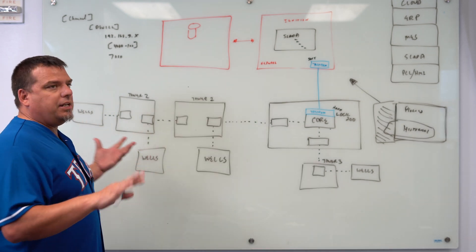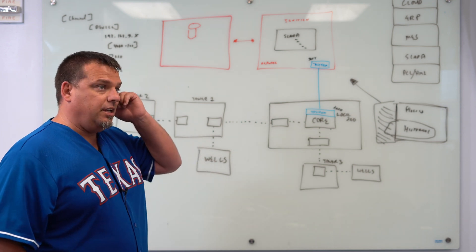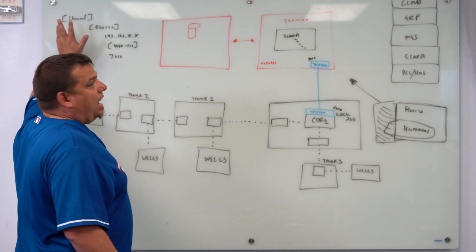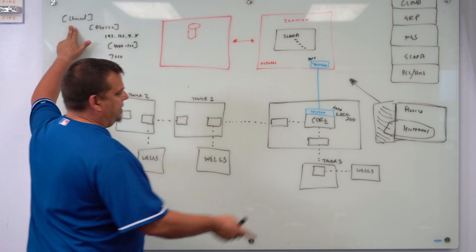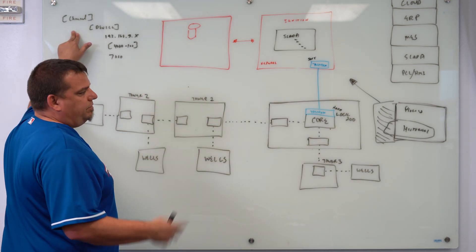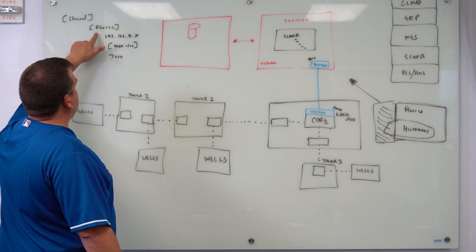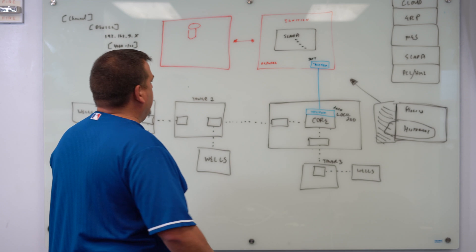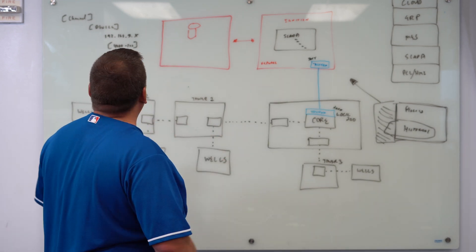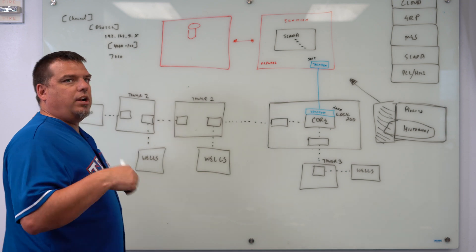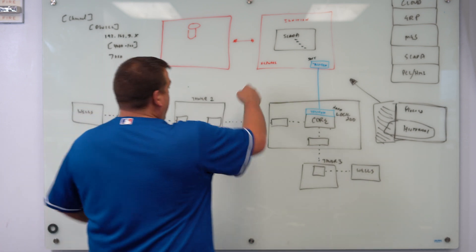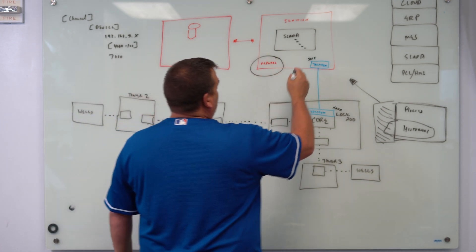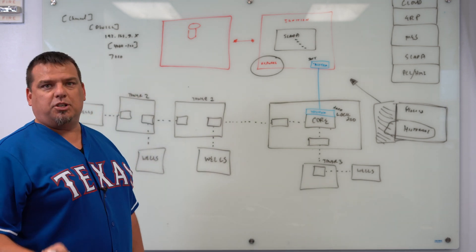The plan right now is we're just about done. We're actually ready to cut over tomorrow. We're going to be doing production testing starting Monday under this existing infrastructure. If you were to look at Kepware, we have somewhere in the neighborhood of - I think we've got a channel configured for every tower. We created a channel for each tower because we wanted to be able to group all the wells by tower for communication diagnostics reasons. We have a channel for every tower, and then we have all the wells listed in the device, or all the ABB total flows under each tower. In the SCADA system, we actually wrote everything kind of very dynamically. We're able to derive the navigational structure from the channel and device structure inside of Kepware just by running some scripts and populating some drop-downs.